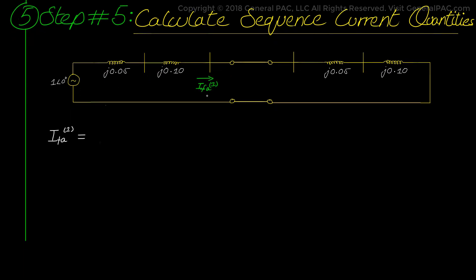The positive sequence current will be the fault current inside the loop which can be found by dividing the voltage with the total impedance in the loop as follows. The pre-fault voltage is 1 per unit at the angle of 0 degrees. And the impedance in the loop is the sum of the positive and negative sequence impedance.